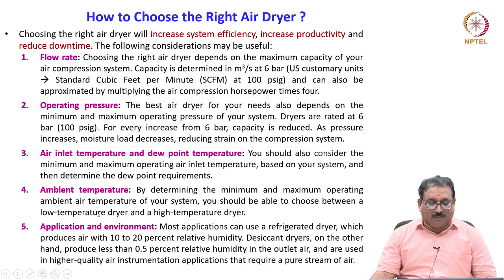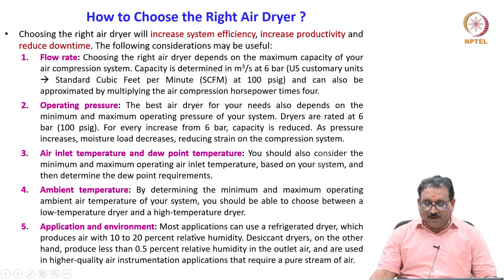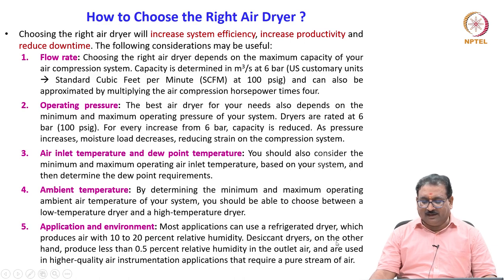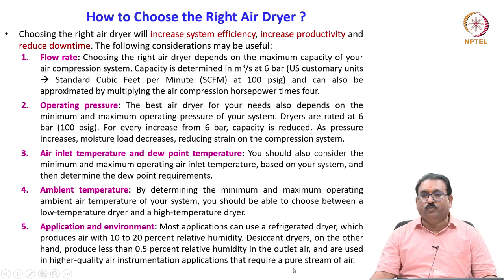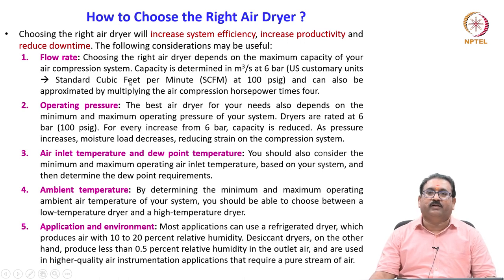Another important parameter is the application and environment where the dryers are used. Most applications can use a refrigerated dryer, which produces air with 10 to 20 percent relative humidity. Desiccant dryers, on the other hand, produce less than 0.5 percent relative humidity in the outlet air and are used in high-quality air instrumentation applications that require a pure stream of air. These are the parameters to consider while selecting the right air dryer for your application.